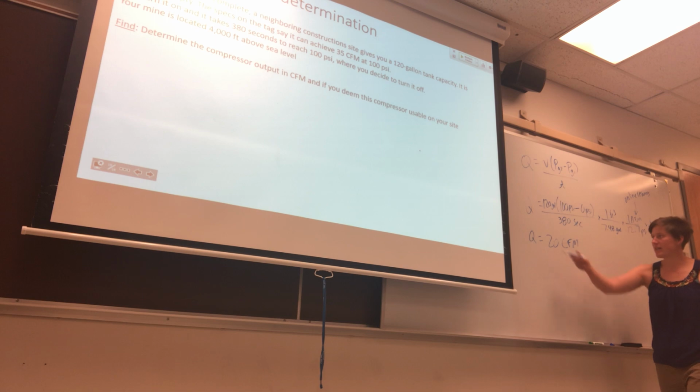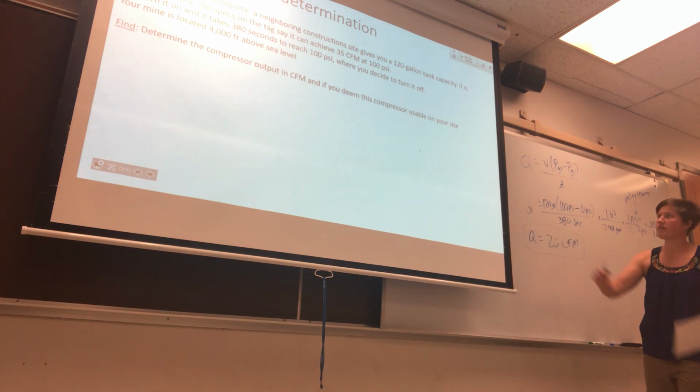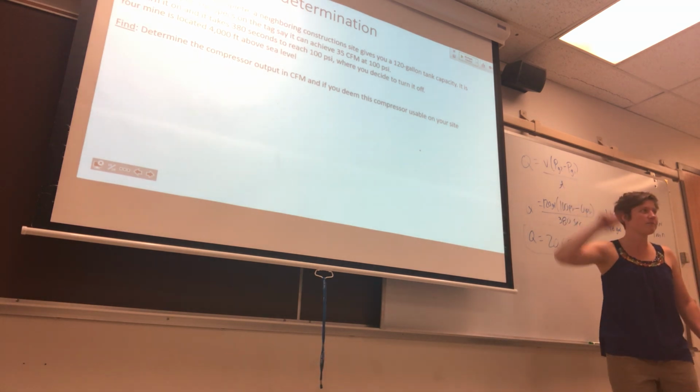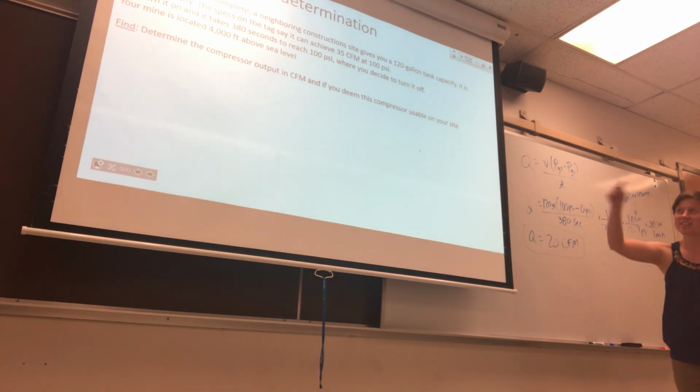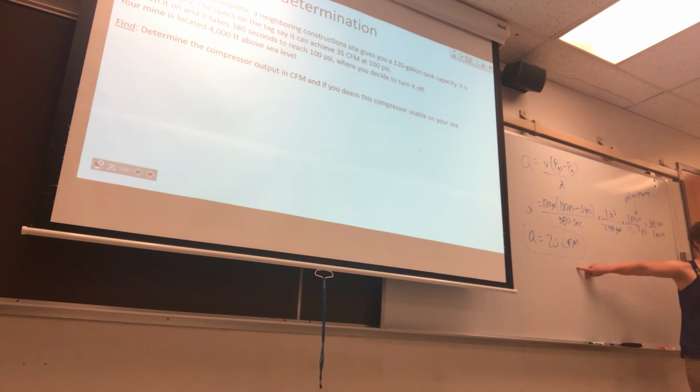Like we calculated it has a 20 CFM, but what does it say on the tag? It's not up to spec. You're right. So it's not exactly that 35, but it's still really good, okay? There's not a huge difference between these two numbers. So would you keep it on site? Honestly, no, because somebody might be trying to screw you over. Yes, Rob's taught you well.